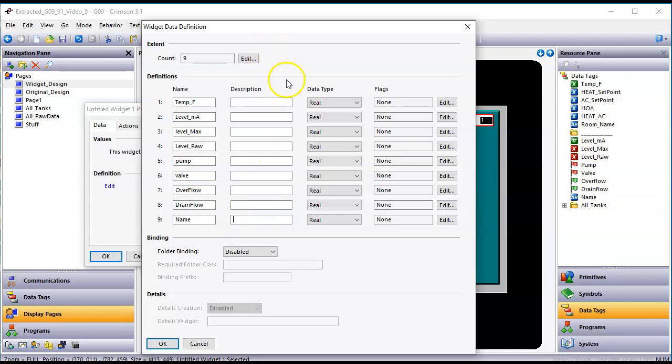All right. Now the data type column basically is what does this tag over here look like? Now if you remember, an X is a numeric type, a pi symbol is a floating point, a real number. The flag tags are a bit on-off. They're part of the integer family. And the tag name over here, AB, is an ASCII string.